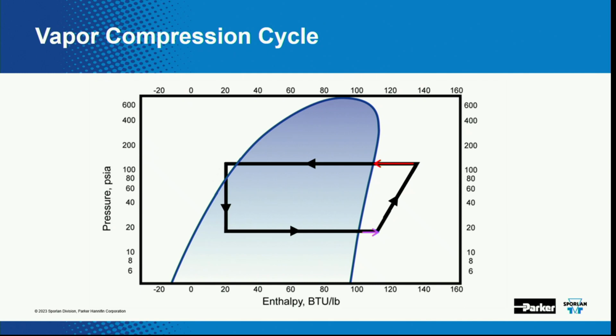So it's taking away the superheat until it gets into the saturation dome, and at that point, it's just cooling. It's condensing and removing latent heat, and it actually goes a little bit over the edge as it's condensing so that it gets into a full liquid state.